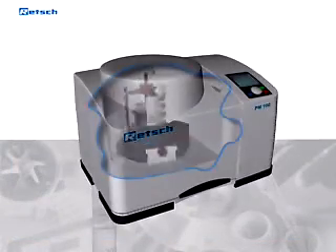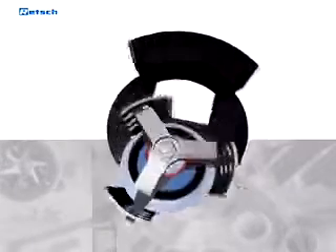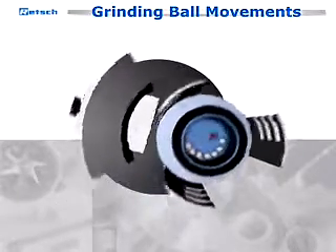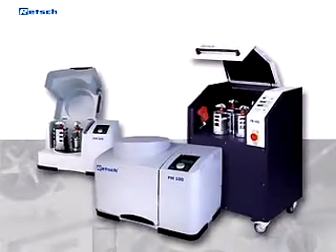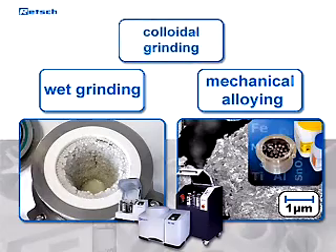In a planetary ball mill, the grinding jar rotates about its own axis and in the opposite direction around the common axis of the sun wheel. This produces grinding ball movements with high pulverizing energy. The combination of impact and frictional forces results in the high degree of pulverization within the planetary ball mills. Retsch Planetary Ball Mills can also be used for wet grinding, mechanical alloying, or colloidal grinding.